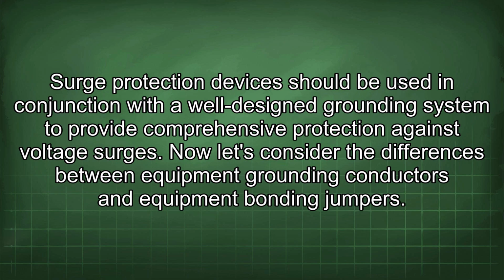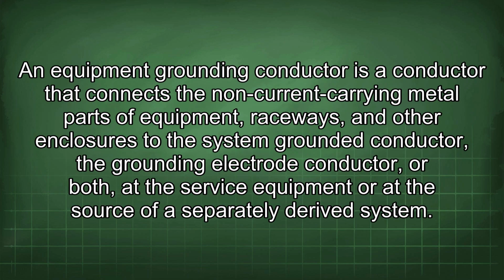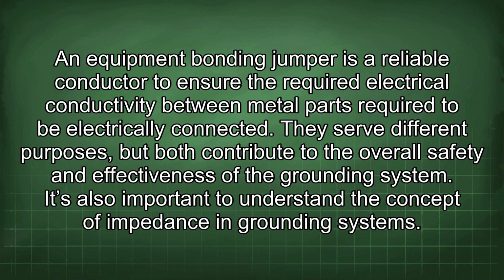Now let's consider the differences between equipment grounding conductors and equipment bonding jumpers. An equipment grounding conductor is a conductor that connects the non-current carrying metal parts of equipment, raceways, and other enclosures to the system grounded conductor, the grounding electrode conductor, or both, at the service equipment or at the source of a separately derived system. An equipment bonding jumper is a reliable conductor to ensure the required electrical conductivity between metal parts required to be electrically connected. They serve different purposes, but both contribute to the overall safety and effectiveness of the grounding system.